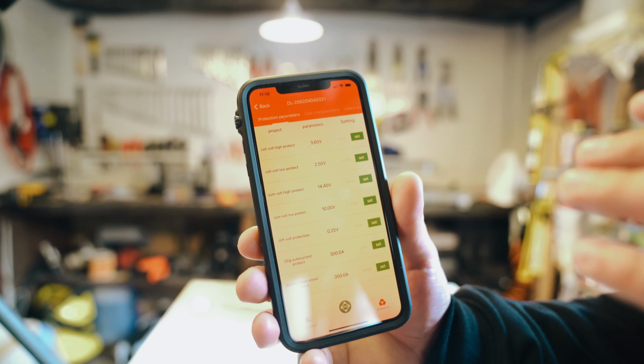Cell voltage low protect, I set that at 2.5. Sum high protect, I put it at 14.4 volts, so it's slightly above that just from balancing the cells, but it'll settle down. From now on, when I charge the battery, the BMS will make sure it doesn't go over 14.4 volts.